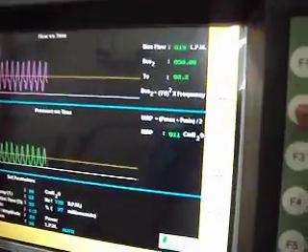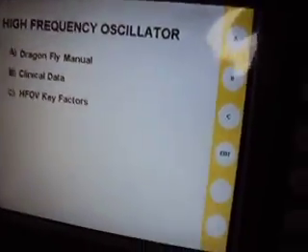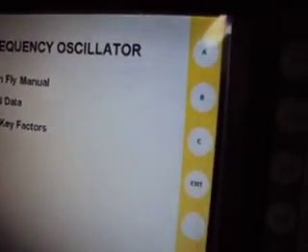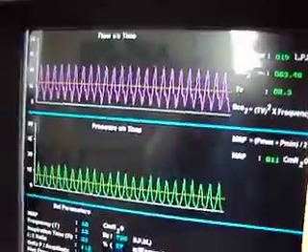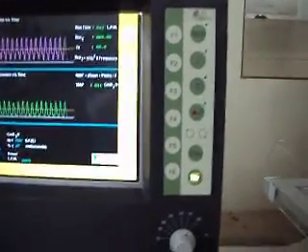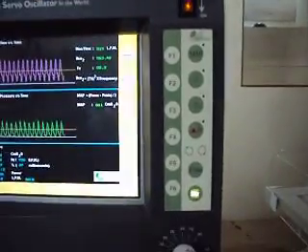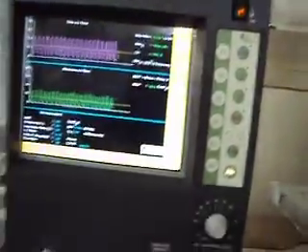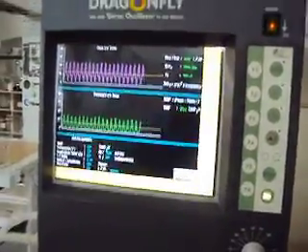Certain features of the product: you do not have to invest in training upfront — training can be done online about what the machine is all about. With the press of the F1 key, one can access either the manual, the clinical data, or the HFOV key factors. You can also freeze these loops and curves for analysis and training. The machine is modular in nature, which ensures very low downtimes, faster serviceability, and low costs of ownership. You do not have to calibrate the piston every time — popularly known as centering the piston — because it is auto adjusted.